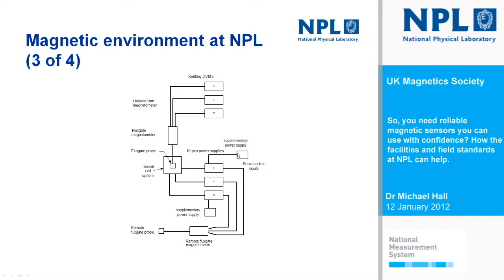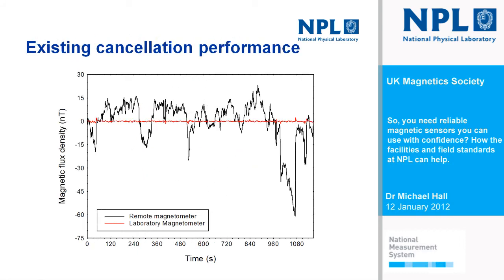What performance is achieved? Well, we see here in this slide the ambient variation is the black line. We see changes there that can be of the order of 100 nanotesla or so over a period of a couple of minutes. And here we have just over 1,000 seconds on the time axis. If we were trying to calibrate a flux gate magnetometer in there which has a noise floor, say resolution, of sub nanotesla, then we would have a massive contribution to that calibration from the background. Even by doing field reversals, that takes a finite amount of time, and this field can be swinging around by tens of nanotesla during that time. So our repeatability would be poor because the background was poor.